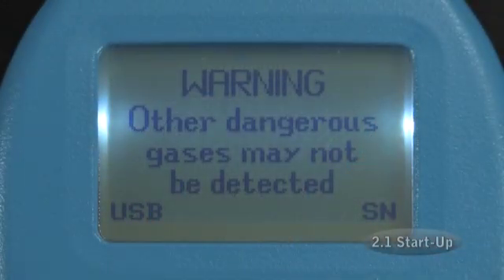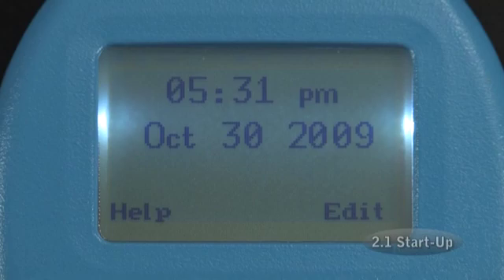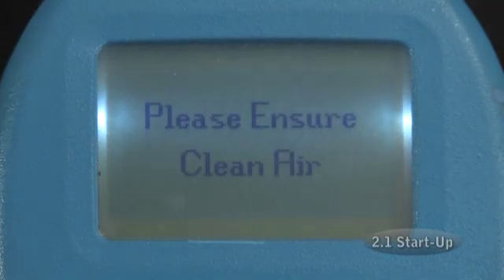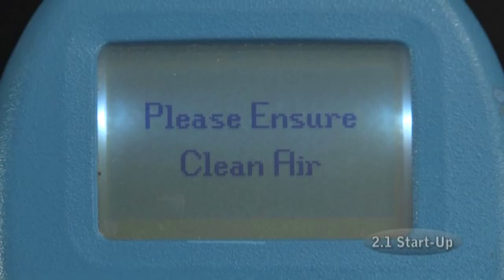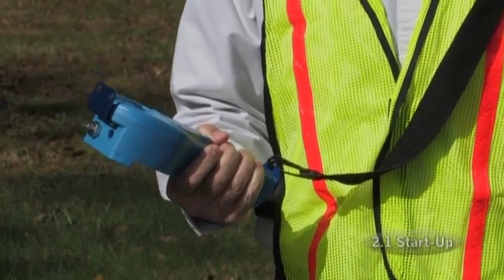If you do not press either button, the Explorer will proceed to the next screen, which displays the time and the date. From this screen, you have the option to access a help menu by pressing the left button under the word Help, or to edit the time and date by pressing the right button under the word Edit. On the next screen, the Explorer will ask you to please ensure clean air. It's important that you first turn on the instrument in clean air, for example, outdoors.